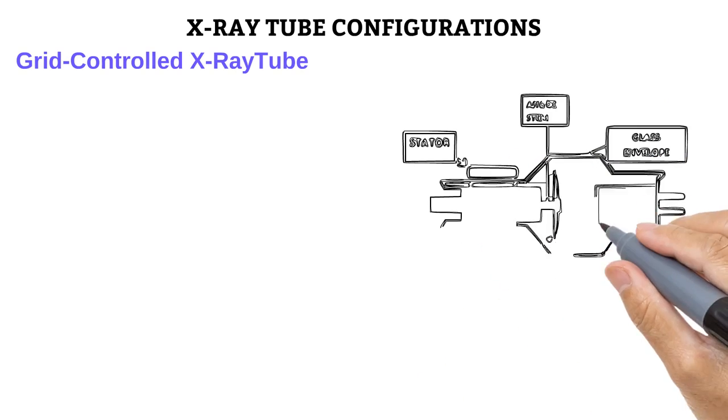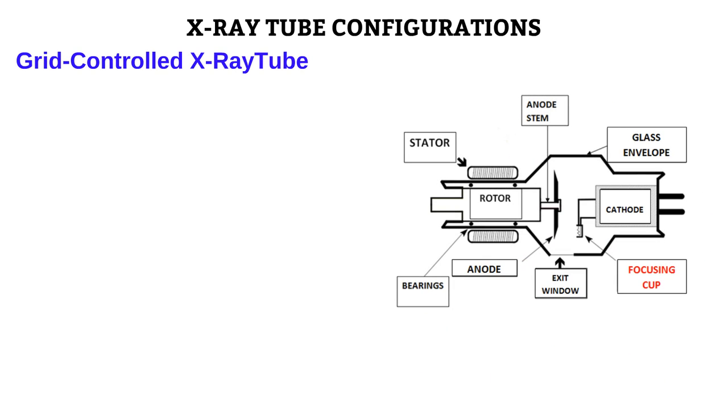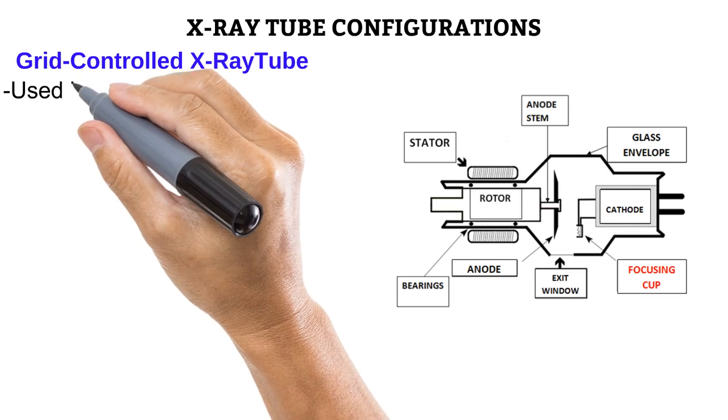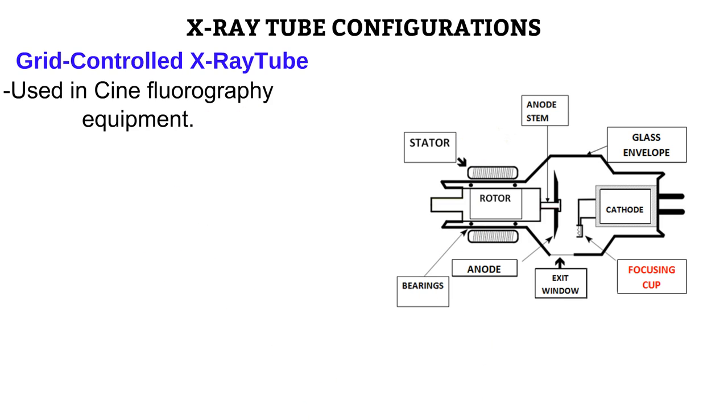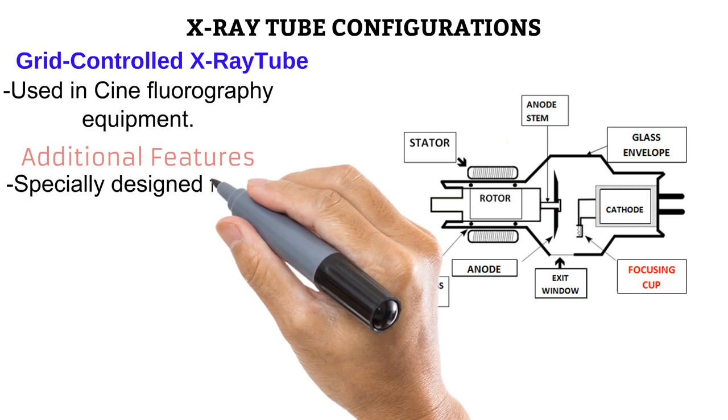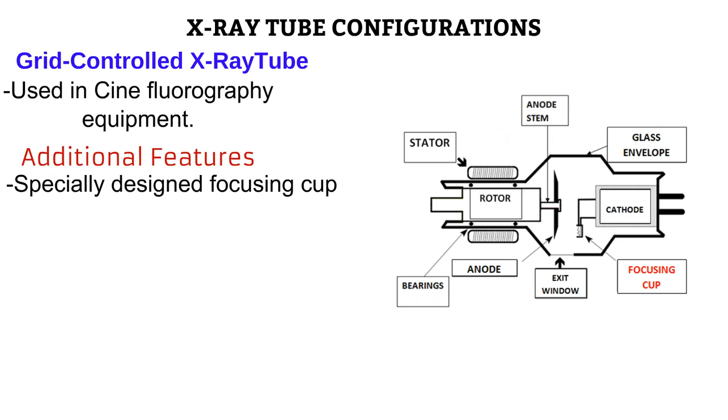The last tube configuration that we'd be looking at is the grid-controlled X-ray tube. This tube is useful in equipment that need to be switched on and off repeatedly and rapidly. An example of which is cine fluorography equipment. Take note that the name has nothing to do with scattered radiation grids. Remember that the normal X-ray tube has two electrodes, the cathode and the anode. In this tube, the focusing cup is specially designed to act as a third electrode. This third electrode would control the flow of electrons from the cathode to the anode. It does this by generating a negative force field. And because same sides repel, this force field repels the negative electrons moving from the cathode filament to the anode.